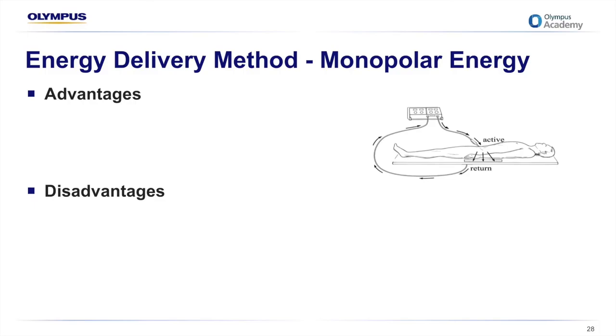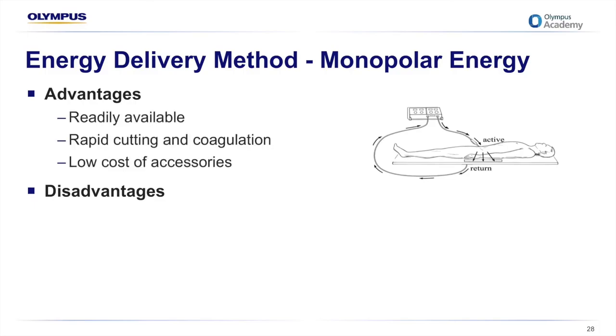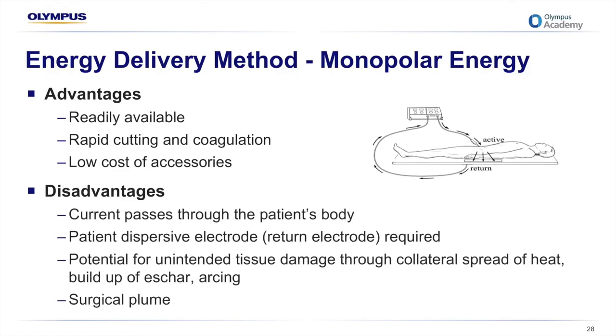Earlier we discussed different energy delivery methods. Monopolar energy is probably the most common type of electrosurgery that we see in the OR. With monopolar energy, we see the tissue effect where the active electrode touches the tissue to either cut, coagulate, ablate or desiccate. We can also see fulguration of the tissue. There's a relatively low cost associated with this energy. Its disadvantages are obvious. Since current passes through the patient's entire body, there's a huge potential for injury, especially if all safety parameters are not met. Collateral tissue damage can also happen through the spread of heat with this technology. And we also see a lot of surgical plume created.